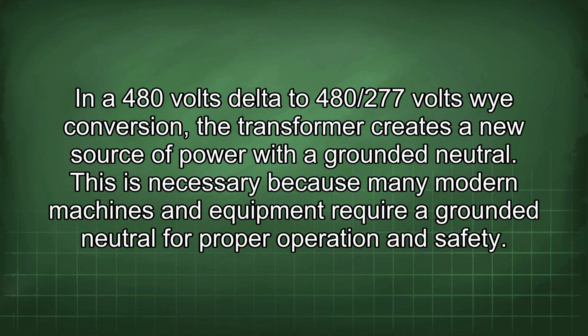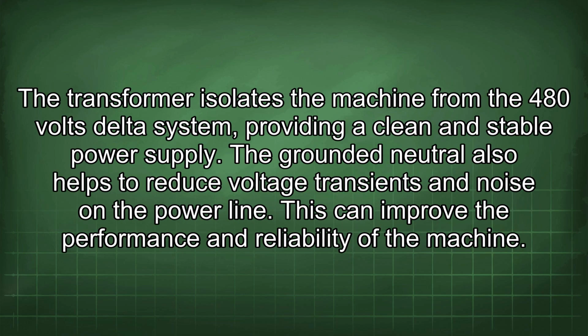In a 480 volts delta to 480/277 volts Y conversion, the transformer creates a new source of power with a grounded neutral. This is necessary because many modern machines and equipment require a grounded neutral for proper operation and safety. The transformer isolates the machine from the 480 volts delta system, providing a clean and stable power supply. The grounded neutral also helps to reduce voltage transients and noise in the power line. This can improve the performance and reliability of the machine.